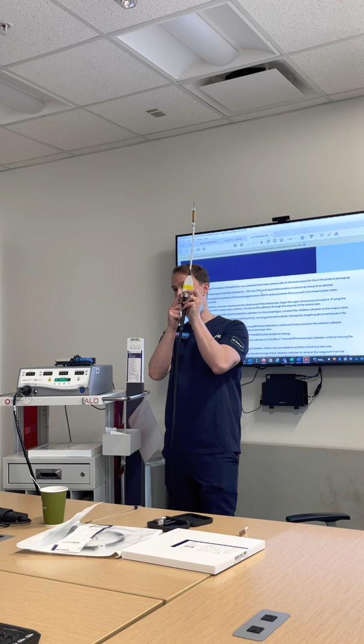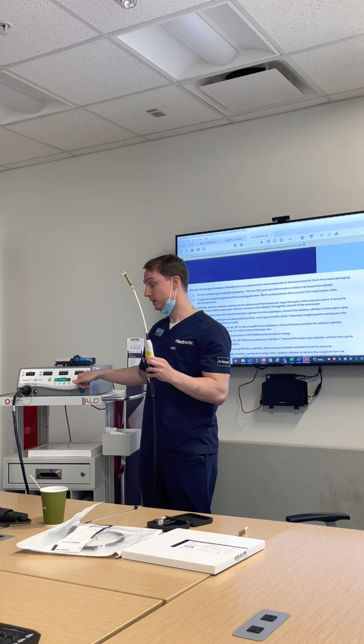Either the plastic filter is not twisted down, this piece is not connected and/or tightened, or we didn't listen to David and we didn't connect this piece. So it's three separate things: the filter, the connection to the filter, or the connection to this system. Once we've done that, if we had an air leak error, that's pretty much the only error that you're going to have with this catheter and/or system in general. Sometimes we'll get a defective catheter. For a defective catheter, you're going to see this. It's not going to recognize the catheter.